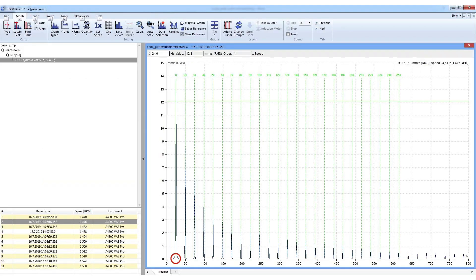How to recognize the exact frequency? The DDS software offers solutions. The first is using the harmonics cursor. Drag the last harmonic cursor and move it to the correct peak. You can see the main cursor position changed — now it is exactly 24.6 Hz.